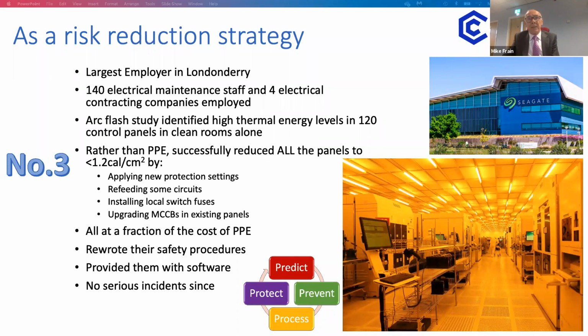I did an arc flash study for that entire site back then. And when we looked at it, we identified high thermal energy levels in 120 control panels just in the clean rooms alone. This is just what they call the fabs. Rather than PPE, we successfully reduced all the panels to below 1.2 calories per square centimetre. And how did we do that? Well, we applied new protection settings to the circuit breakers.